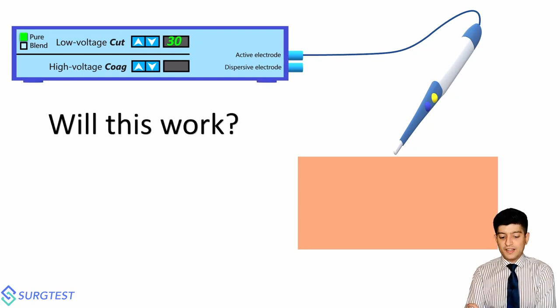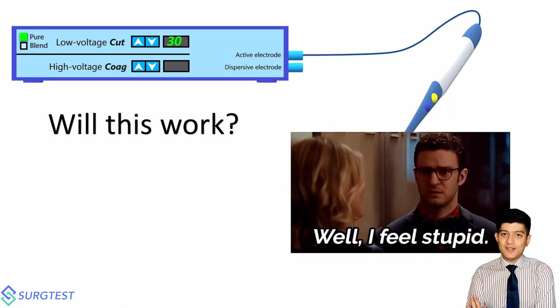Now, is this going to work, this arrangement that you see on screen? The answer is of course not, right? The circuit has not been completed. So it's not going to work. What you need is a dispersive electrode for the circuit to be complete. Now remember, all radio frequency energy is bipolar. Okay. For example, even in the monopolar diagram that you're seeing, there's one pole here, another pole there. There are always going to be two electrodes involved.